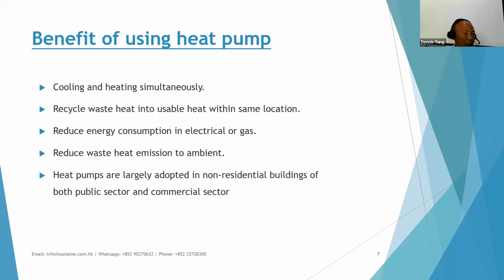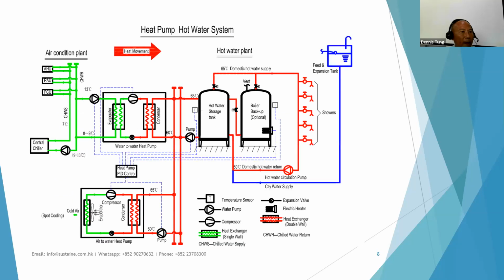So nowadays, heat pumps are widely adopted in non-residential buildings, both in government projects and in the private sector. So here is a system demonstration in a building. Basically, on the left side is the air conditioning system. On the right side is the hot water system. A heat pump is the equipment that connects both the air conditioning system and the hot water system, and it absorbs the heat from the air conditioning system and transfers it to the hot water plant. So therefore, energy is locally recycled and used on the hot water side.